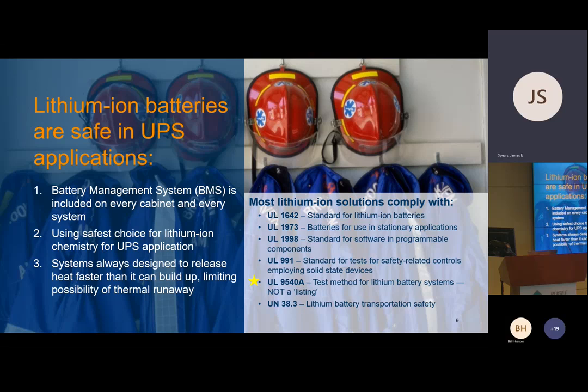A couple steps down, UL 9540A is not a listing—there is a listing called UL 9540 without the A—but UL 9540A is simply a test method for verifying that if I light a lithium battery cabinet on fire and watch it burn, the flames will not propagate to any adjacent cabinetry, the wall, or the corner where it's placed.